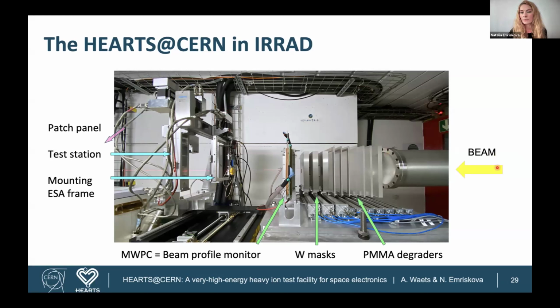So we have the beam coming here from the right. You see a portion of the vacuum pipe. Just after, we have a set of PMMA degraders to adjust the beam energy locally. We also have a couple of tungsten masks to shape the beam, and the beam profile monitor to visualize the beam just before it reaches the component to test. And here you see our new test station, which is used with the so-called ESA frames, where you can mount the devices for the irradiation. And the patch panel to connect the devices to the outside is here outside of the picture, just here on the wall.